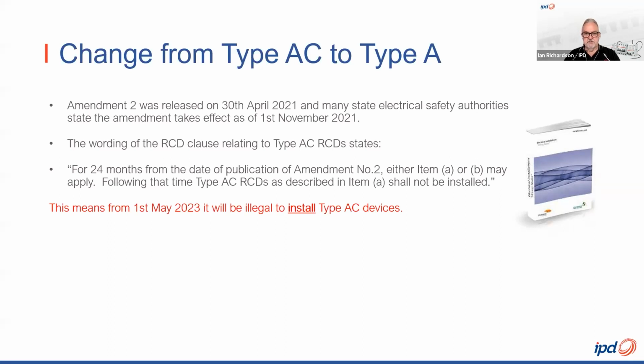But there's an exception. To be absolutely clear, the amendment states that in relation to type AC RCDs, for 24 months from the date of publication of the amendment, items compliant with Part A and Part B, as we spoke about, can be used. Following that time, type AC RCDs shall not be installed.